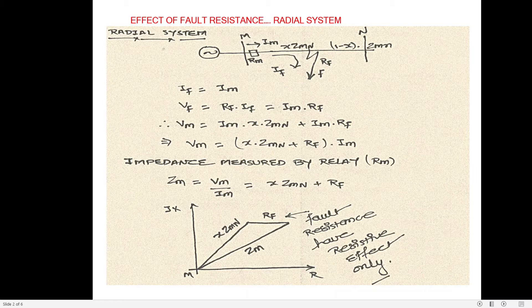X·ZMN is the fraction of impedance up to the fault point F with fault resistance RF. The fault current flows, and (1−X)·ZMN is the remaining impedance from the fault point to bus N. RM is the relay at bus M. The current measured by relay RM is IM, and IM equals IF.